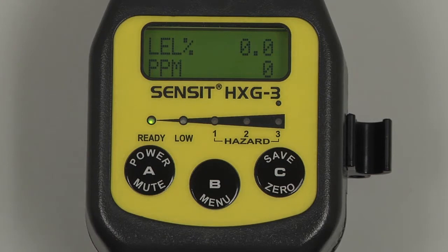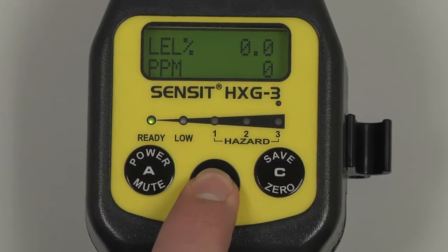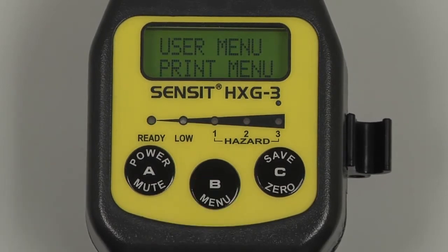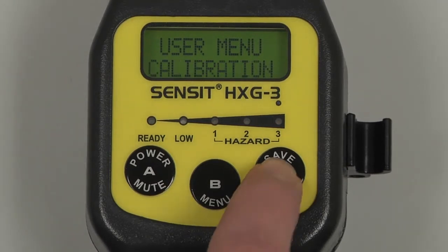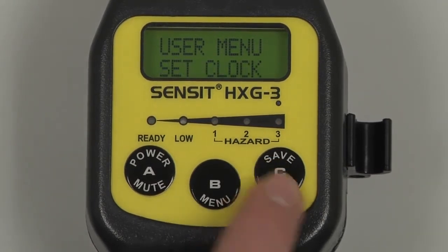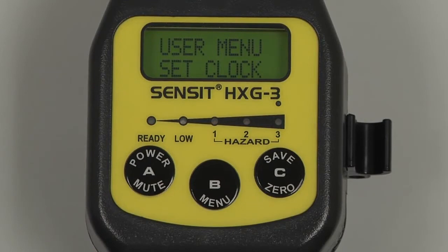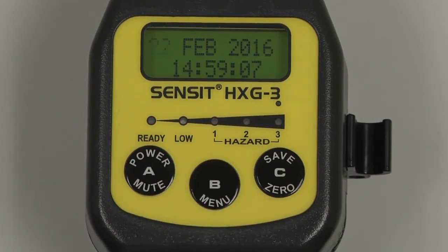Before calibrating, we must verify the date and time and perform a flow check. To verify the date and time, enter into the user menu by pressing and holding the B button, and scroll through the menu by pressing and releasing the C button until set clock appears. Select by pressing and releasing the B button, and the date and time will be displayed.